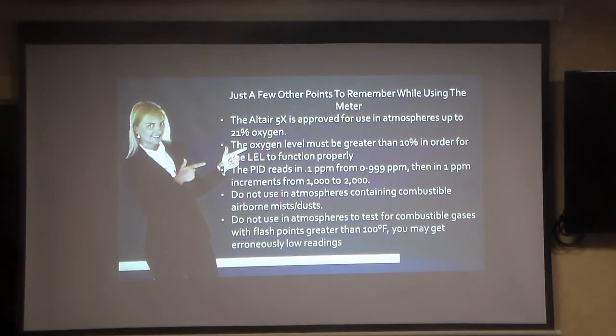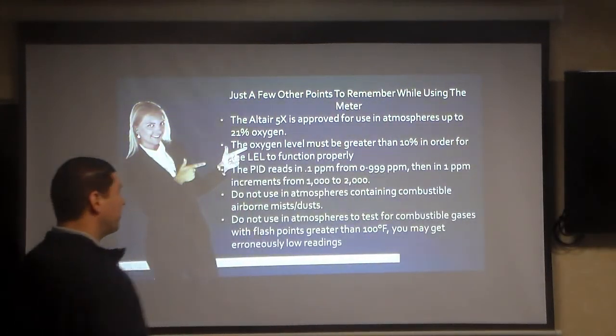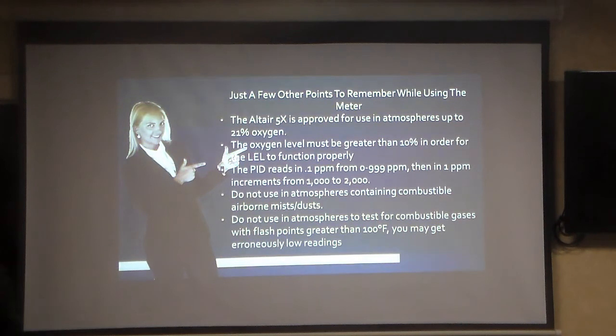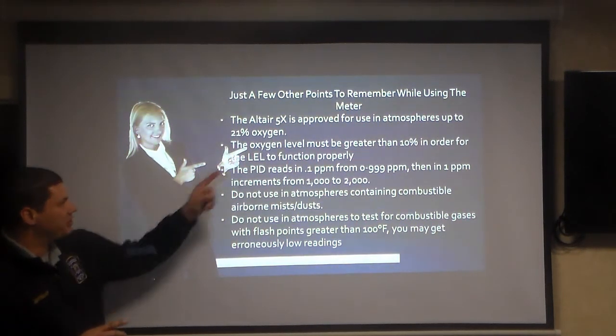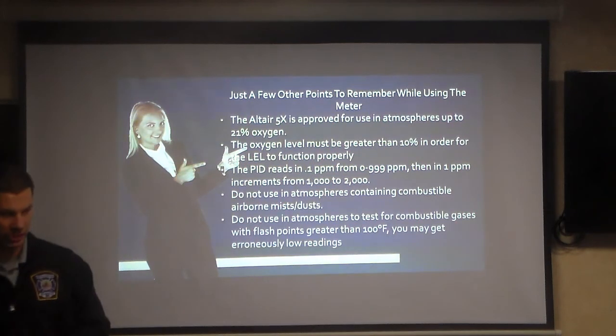Here's a few points to remember when using the meter. The Altair 5X is approved for atmospheres up to 21%. Doesn't mean you can't, but the LEL is not going to work if the oxygen is too high. The oxygen has to be greater than 10% for the LEL to function.